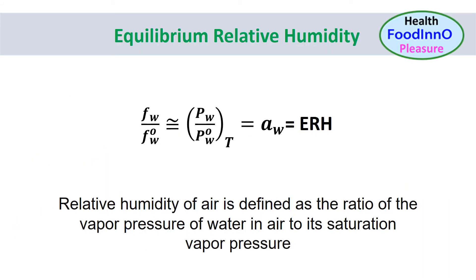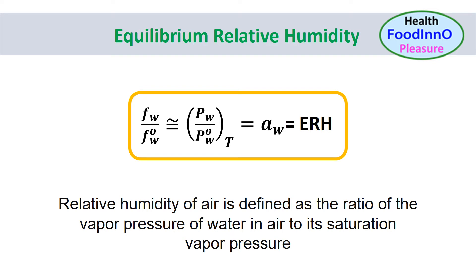When vapor and temperature equilibrium are obtained, the water activity of the sample is equal to the relative humidity of the air surrounding the sample in an airtight chamber. Relative humidity of air is defined as the ratio of the vapor pressure of water in air to its saturation vapor pressure — that is, the water content in air relative to its maximum water-holding capacity.